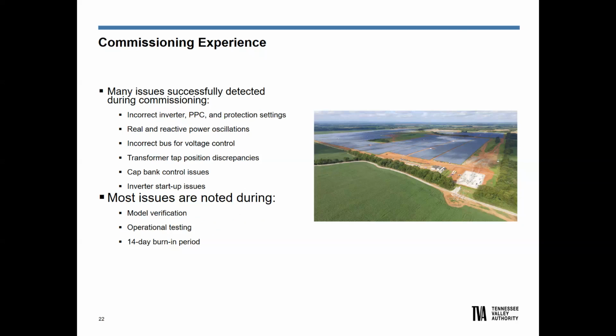Also, inverter startup issues. So the cap bank issues could be, we've seen people turning them off too quickly, coming off before they need to and dropping the voltage too much, or turning on cap banks even before they've been generating from the inverter as well. Inverter startup issues, we've seen trying to start too early with no sun or not enough sun, they'll drop right back off, maybe even several different times, starting too soon and too quickly and dropping back off. We also had issues starting early with another plant. The plant would not trip, but kept having severe reactive oscillations, which could be even worse because we're seeing some flicker on the bulk electric system.